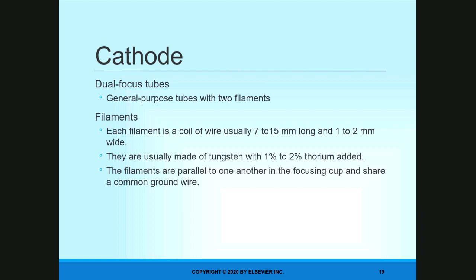How that plays out is that with a smaller focal spot, you tend to use more time, and when you use a larger focal spot, you use less time. With larger areas like the trunk, the chest and the abdomen, the reason we want to use large focal spot and less time is to reduce the chance of the patient moving.